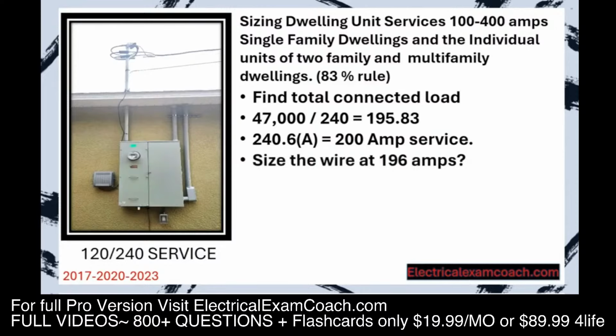Now the next step normally would be to size the wire at 196 amps, right? That's our known load. We can just follow our normal ampacity rules. Well, not with services that are in between 100 and 400 amps. And let me show you what I mean.